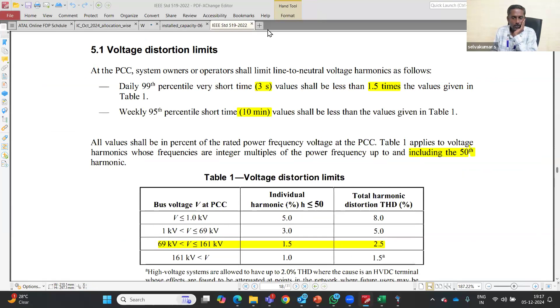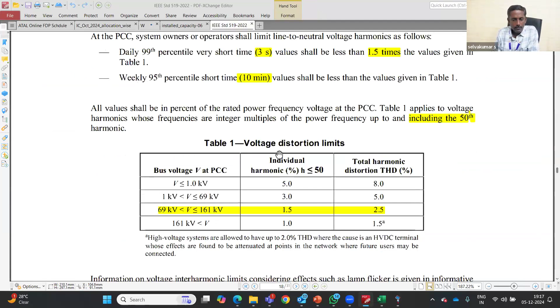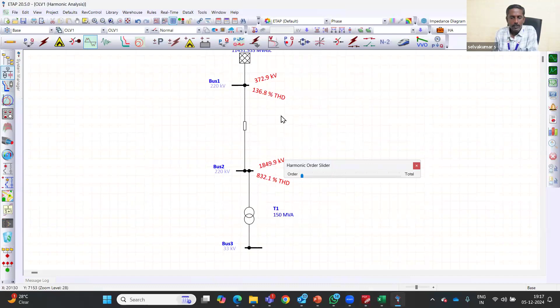Let me open the IEEE 519 document as well, the latest document. So this IEEE 519-2022 gives the voltage distortion limits. If your system is connected at less than 1 kV, individual harmonic distortion should be less than 5% and total harmonic distortion should be less than 8%. If your bus voltage is between 1 kV and 69 kV, individual harmonic distortion is 3%, total is 5%, 69 to 161 kV, 2.5%, all these things. And this is what you need to benchmark with the simulation, whether you are able to meet it or not.